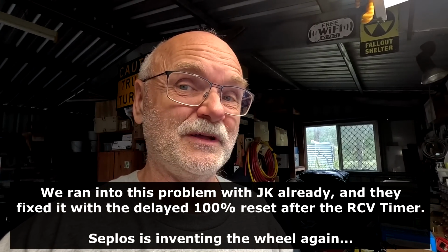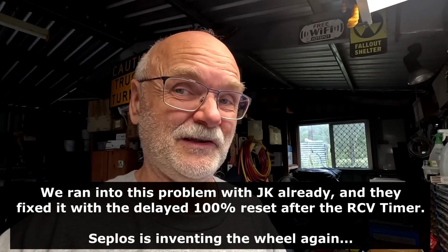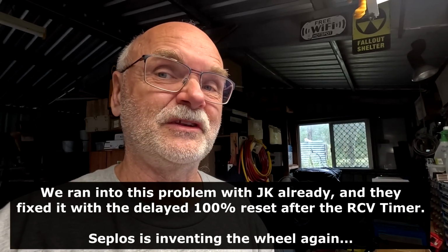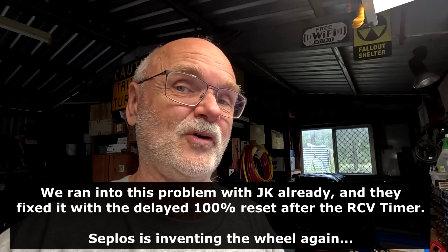If you have an inverter looking for the state of charge of the battery, it will stop charging this battery immediately. This is why we changed it in the JK BMS after the absorption timer, because otherwise these batteries will never see any absorption time. Usually you have a load connected, and if the inverter stops charging your battery, the load will discharge your battery immediately, and there will be no absorption, no balancing happening, nothing. This is potentially an issue you will see with version 3 and this firmware here—you won't see any absorption time or balancing.